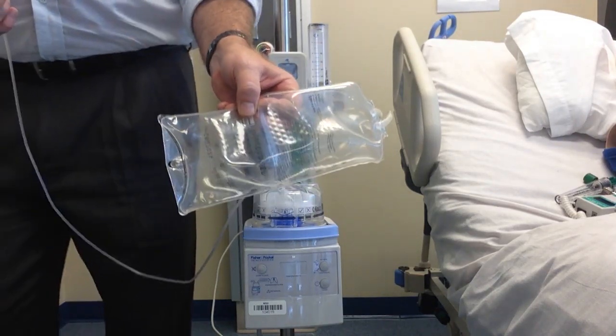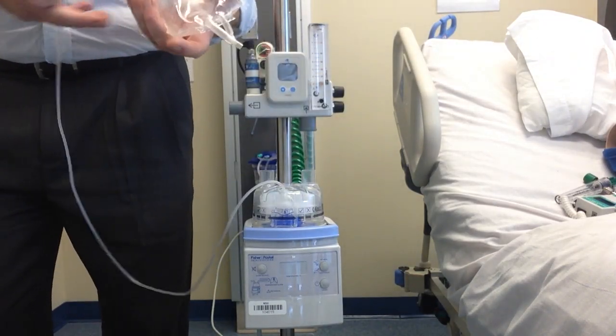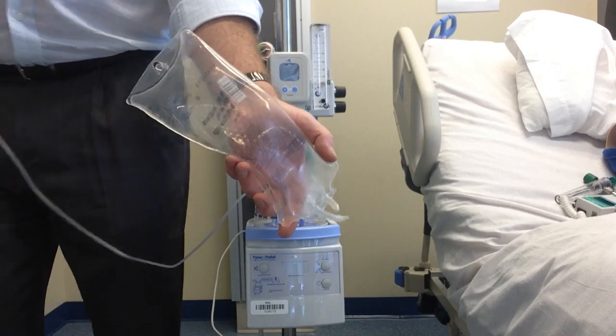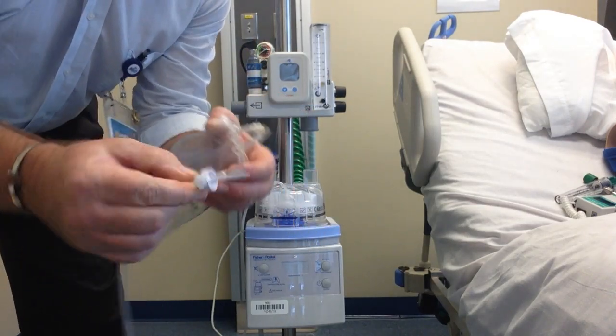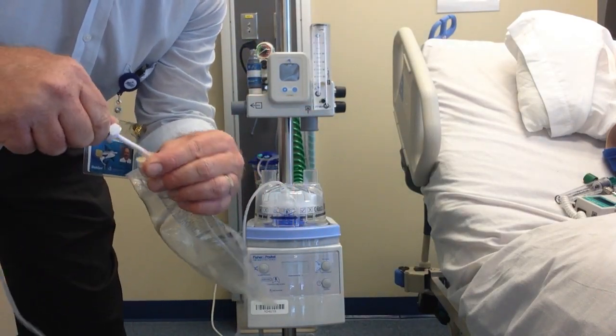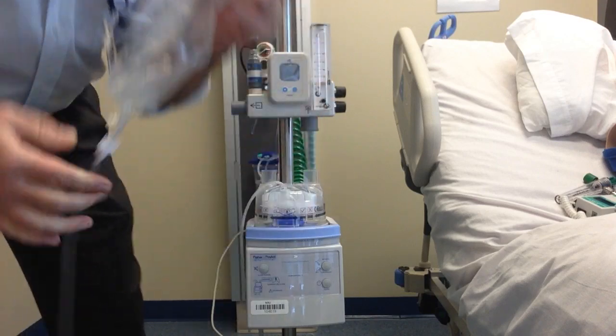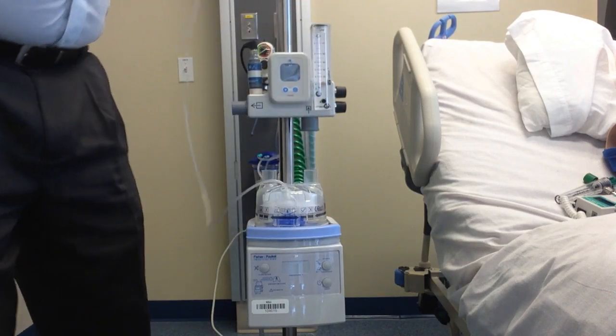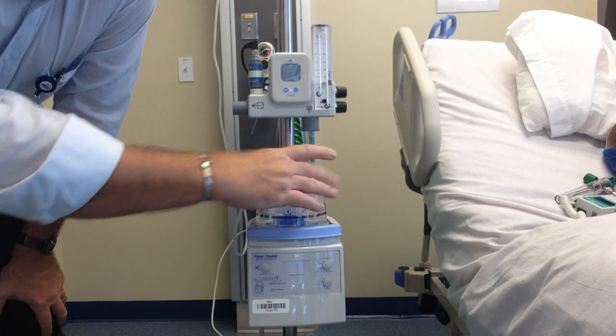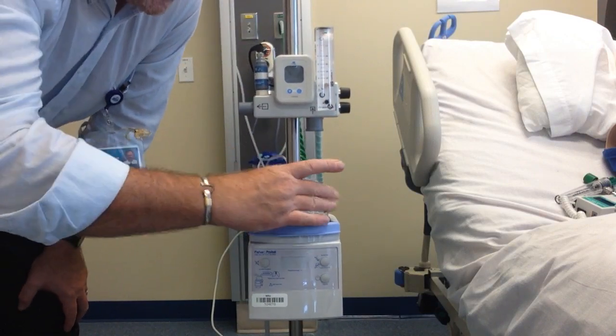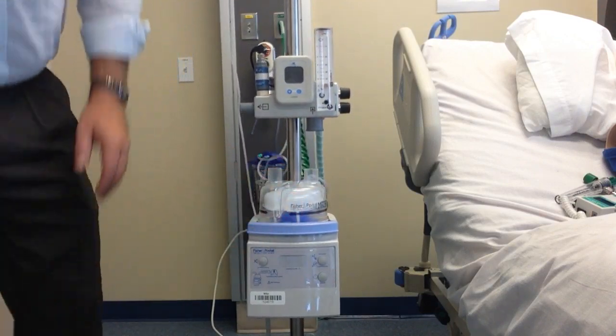You will then take your water bag that you get from Central Supply or from the supply closet. This bag is 1 liter sterile water. This has a spike. You pull it out, and then we'll spike the bag and hang it up. The humidification chamber has a float in it so it does not overfill. Right now we're just setting this up.